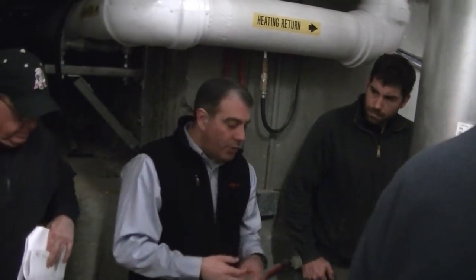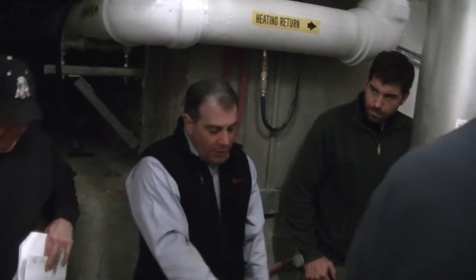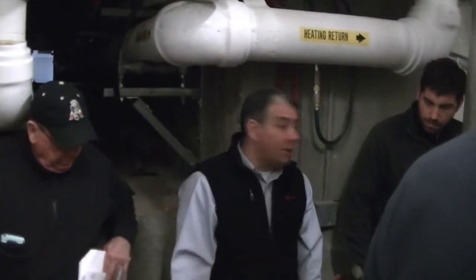Now, I know we don't have the issue here, but if you're in a building that has a septic system and you're dumping that low pH into a septic system, you actually kill the bacteria in the septic system and you stop the bacteria from doing its job. So it's important to make sure that we're neutralizing it. If you come in here and the lime pellets are nice and white and clean and they're full, you shouldn't have any issue with the right amount of pH coming out the other side.